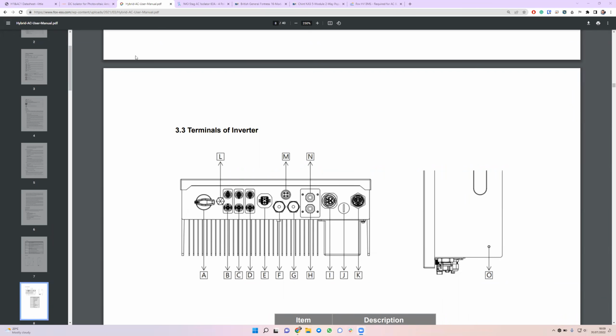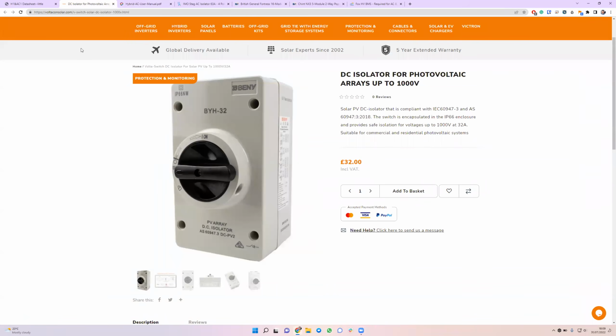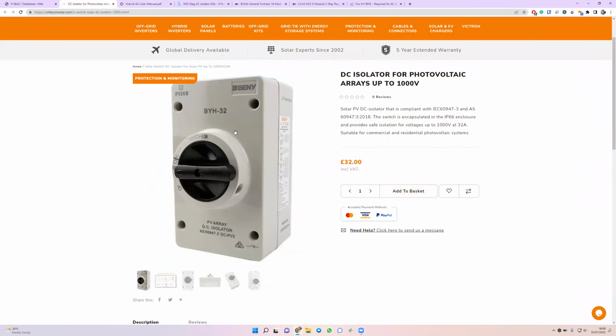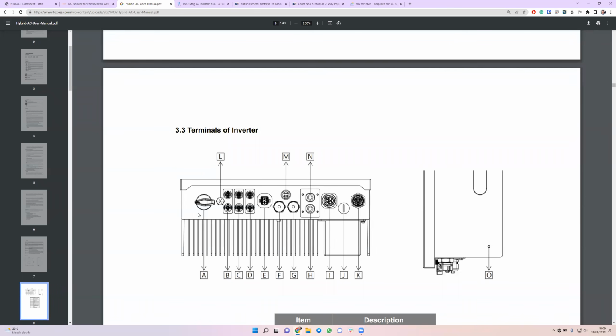I prefer to have both, a box like this, where the cables coming from the solar panels go into and then leave and then connect into the inverter. But if you don't have one of these, and you're following the black cables coming from your solar panels to your inverter, and there is not one of these in between, then most likely your installer is utilizing the built-in DC isolation function, which is this knob here. The box is mounted on the wall facing you, looking at the screen. It's in the left-hand corner. You'll feel it, and you'll be able to turn it to disengage.